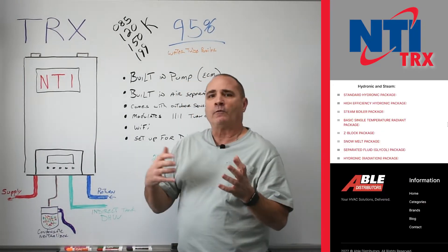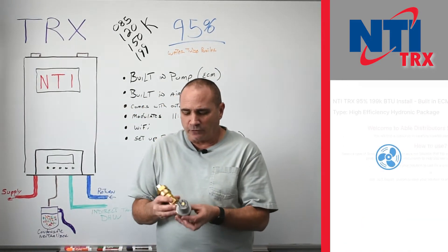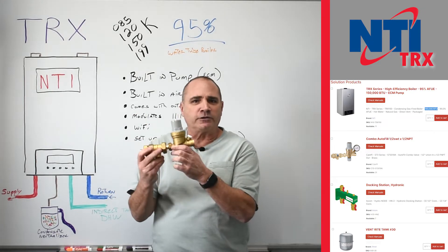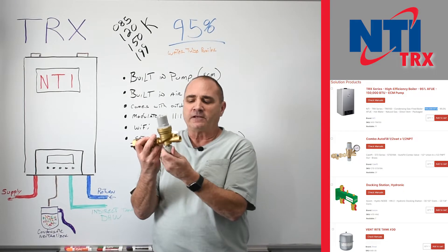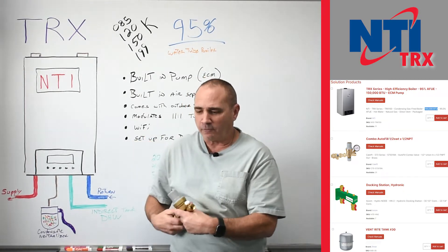Some of the accessories you're going to want: you've got to fill it and regulate how much water pressure goes into the system, and have a backflow preventer. This one is from Caleffi — it's got an on/off valve on the bottom and you actually set the PSI at the top.